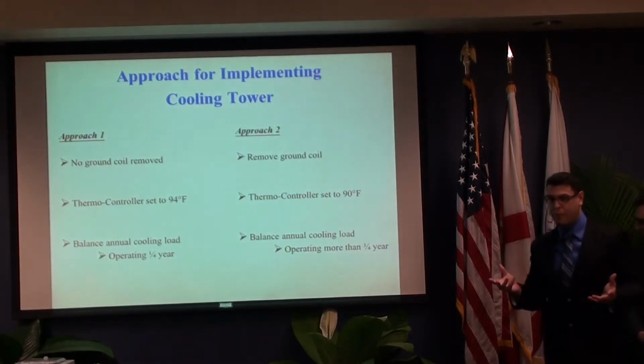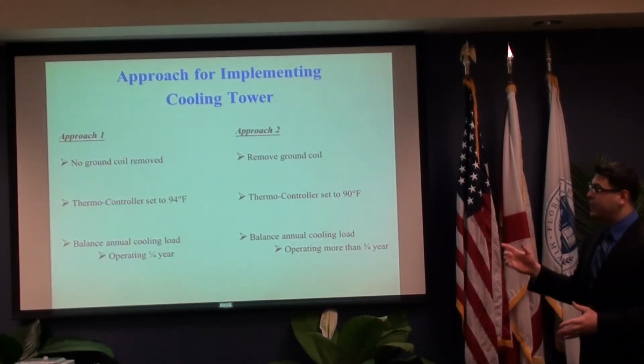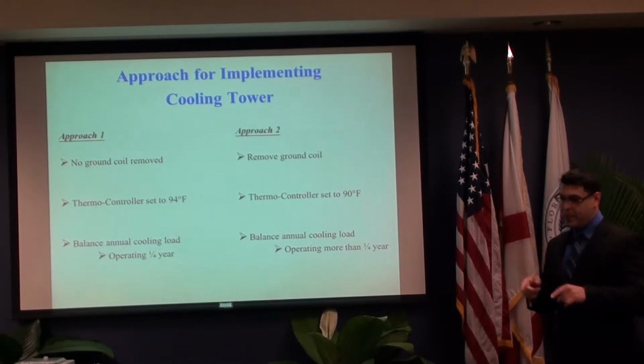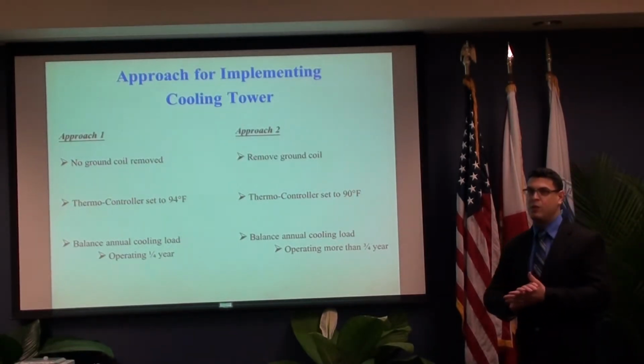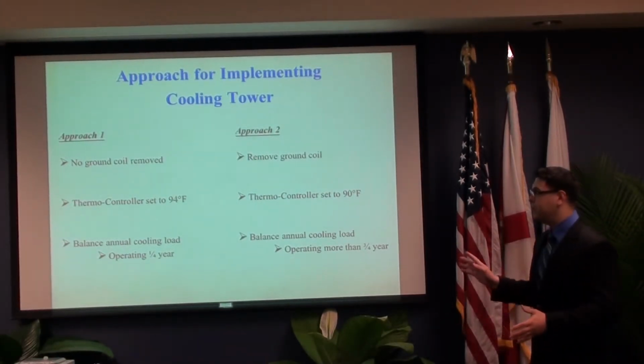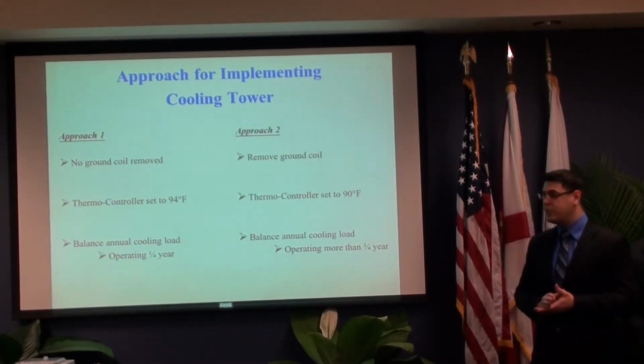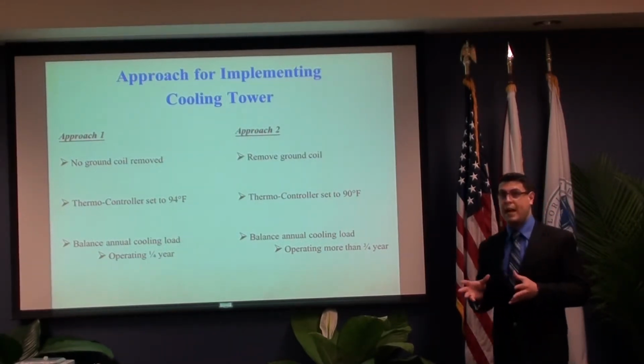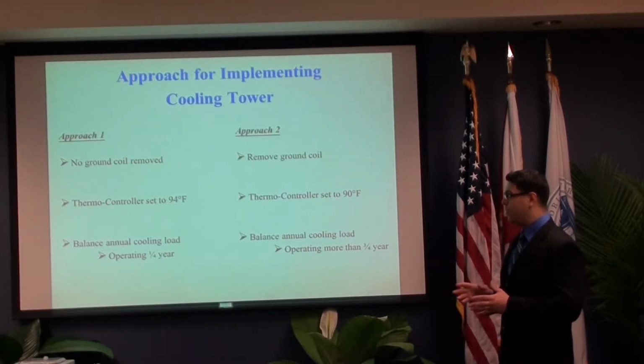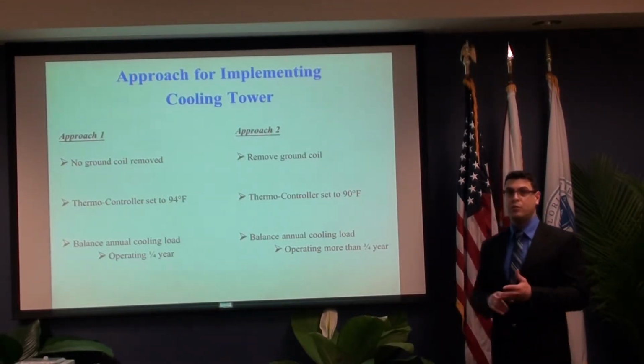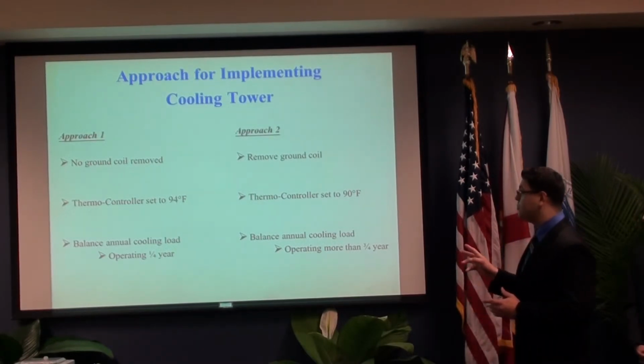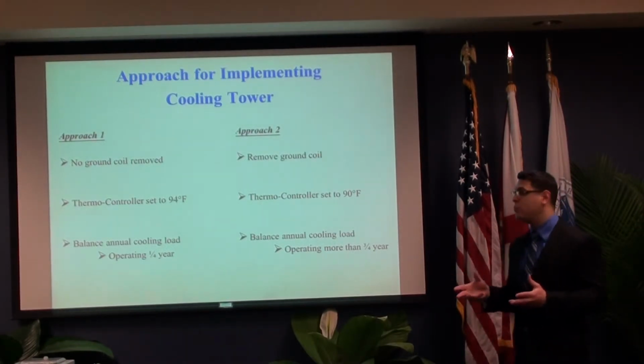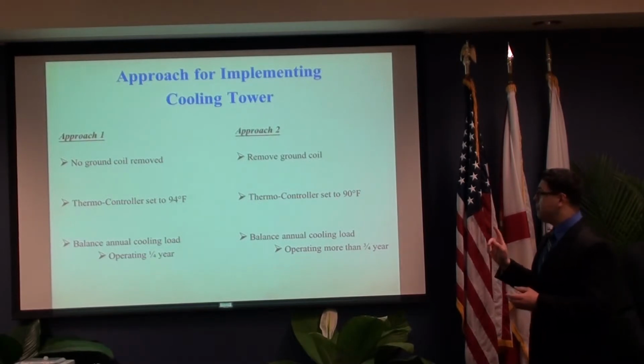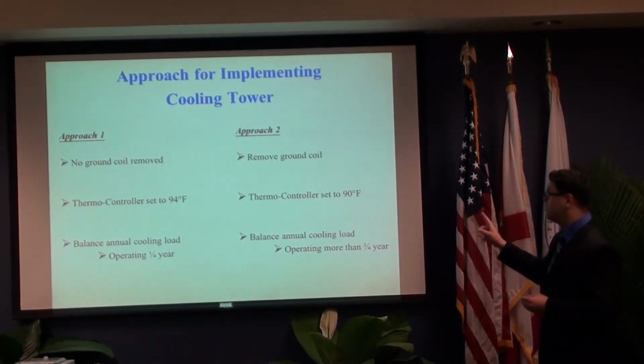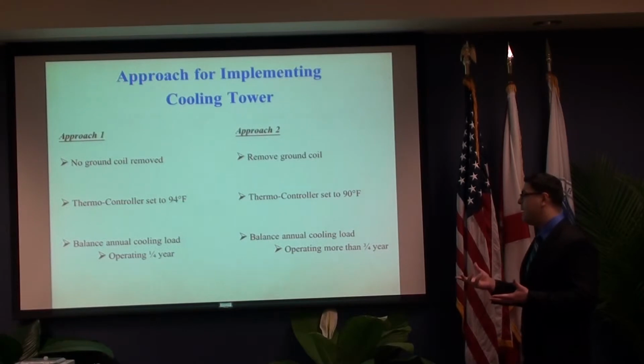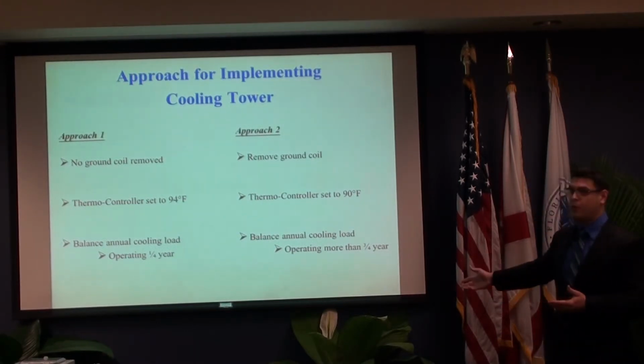We have 2 approaches for implementing this cooling tower. The first one is to use this cooling tower and place it right now with the FIU solar house and to not remove any ground coils at all. This means that we'll set the thermal controller to 94 degrees Fahrenheit, and we're going to be balancing the annual cooling load 1/4 of the year, meaning the three hottest months of the year, June, July, and August. The second approach is to remove a substantial amount of ground coil and replace it with the cooling tower. By doing so, we can set the thermal controller to 90 degrees Fahrenheit, and we'll be balancing the cooling load for more than 3/4 of the year.